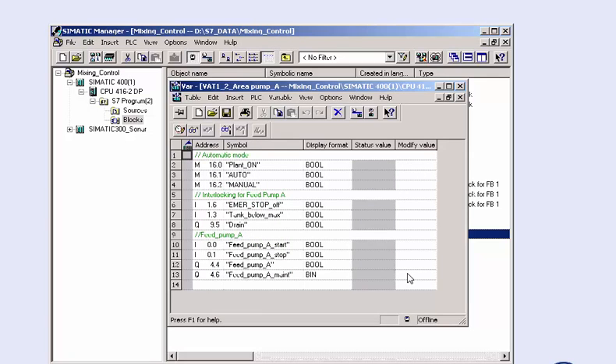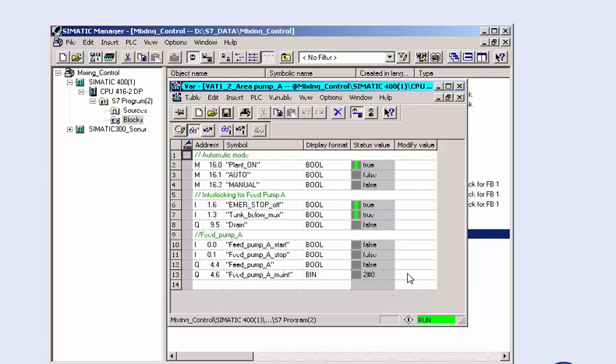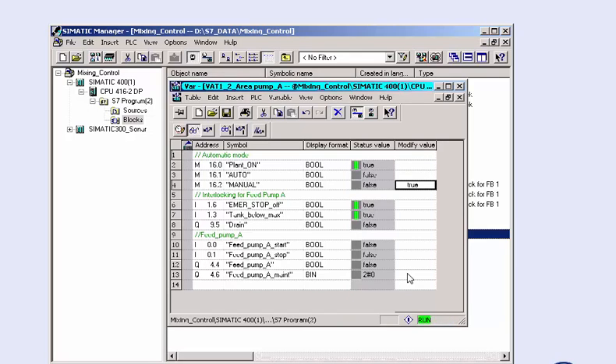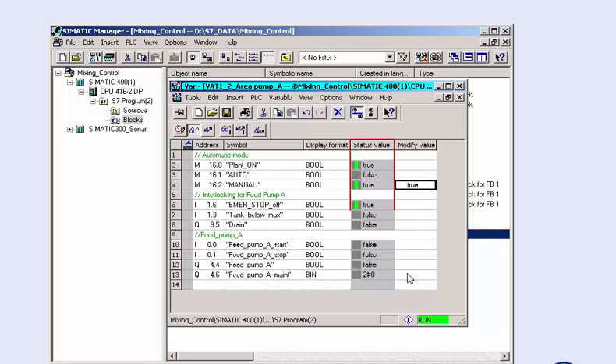In order to work with a variable table, we switch it online with the monitor variable button. Now you can monitor the status values of the listed global variables and define modify values. To do this, you enter the control value true and press the modify variable button. The signal change is directly displayed in the status value column, which in online mode displays the current signal status.